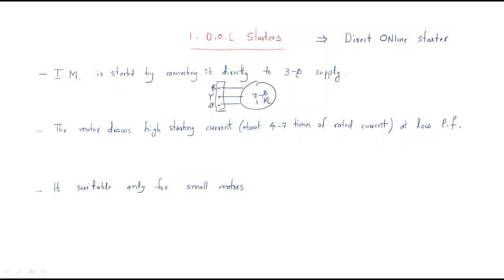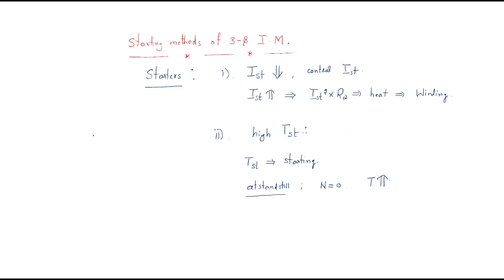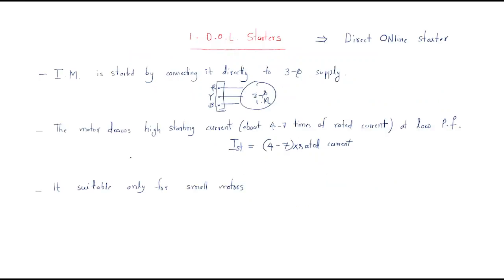The motor draws a high starting current — about four to seven times the rated current — at low power factor. Without any control, the starting current is very high. We already discussed the two requirements: controlling starting current and improving starting torque.